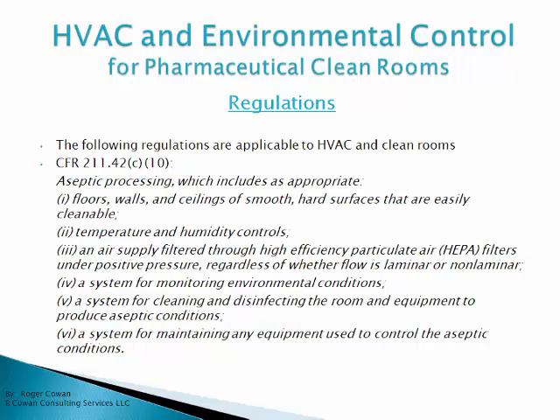What are the regulations concerning pharmaceutical clean rooms? GMPs — CFR 211.42c — states aseptic processing includes, as appropriate: floors, walls and ceilings of smooth hard surfaces that are easily cleanable; temperature and humidity controls; and an air supply filtered through high efficiency particulate air, or HEPA, filters under positive pressure, regardless of whether the flow is laminar or non-laminar.